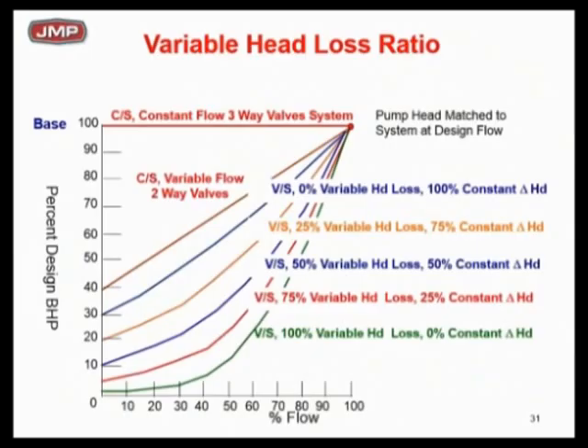What happens as you change the relationship of total pump head — variable versus constant? On this diagram, the left vertical axis is horsepower and the bottom axis is flow. The bottom green line represents what variable speed drive theory promises: 100% variable head, 0% constant head. At 50% flow on that green line, I'm at one-eighth horsepower — that's what you were promised, but only if you have 100% variable head.